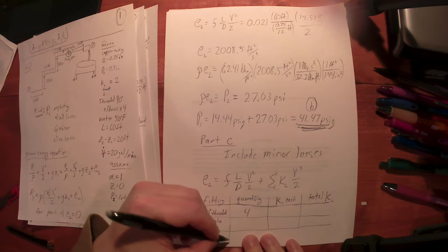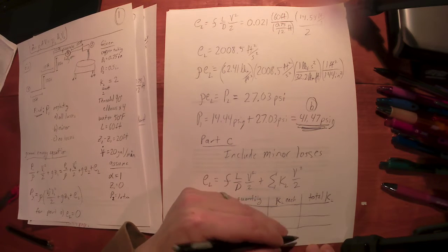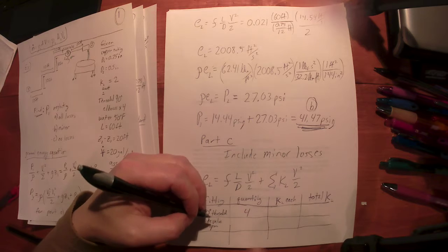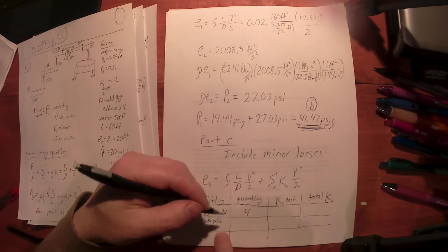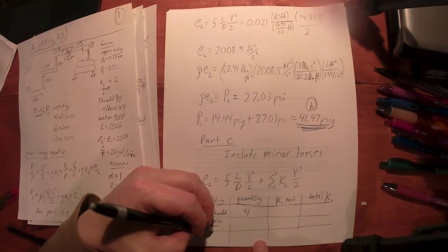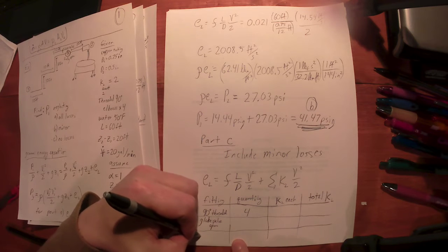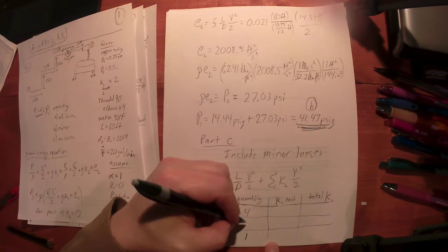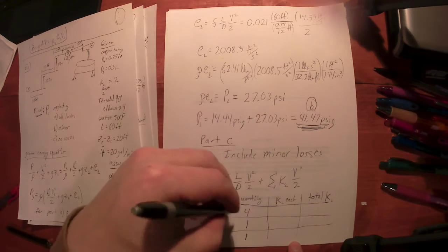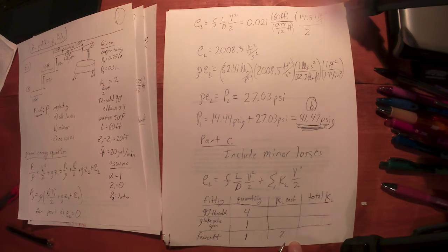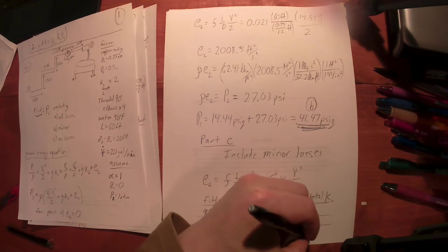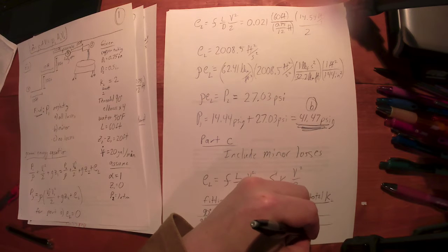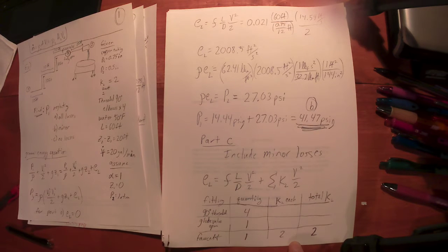and the reason this is going to be overkill on something this simple is because I've just got a few entries. But if I've got a really complex system with lots of unions, lots of elbows, lots of valves, you probably want to build a table to do this. And I've got this faucet. I've got 1 of each of these. We know the faucet has a minor loss for each faucet of 2, and there's only 1 of those, so that's a total minor loss of 2 on that. The others we need to look up. Okay? And that's marked in my text here.